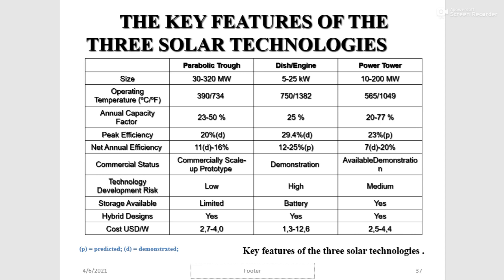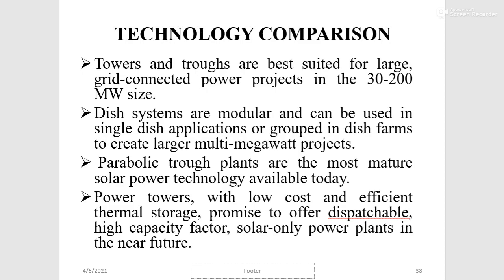In terms of technology comparison, towers and troughs are best suited for large grid-connected power projects in the 30 to 200 megawatt range. Dish systems are modular and can be used as single units or grouped in dish farms to create larger multi-megawatt projects. Parabolic trough plants are the most mature solar power technology available today. Power towers with low-cost and efficient thermal storage promise to offer dispatchable, high-capacity-factor solar-only power plants in the near future.